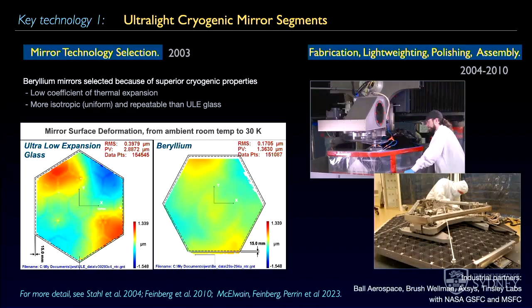We do this with something called wavefront sensing via phase retrieval. And the cartoon version here is that you take light and you focus the light down, and you want to take not just the picture of a star or a point source, a calibration light source, when the light is in focus, but also when it is before focus and after focus. And you can use the information content and the blurriness, the defocus of this, to back out what the exact state is. And you can imagine, of course, those of you that wear glasses, you go to the doctor and they put different lenses in and you measure, is this better or not with the lens in or not. We're doing that modeling with computers to simulate the propagation of light and to fit a numerical model that gives us very precisely, with nanometer precision, the state of light.